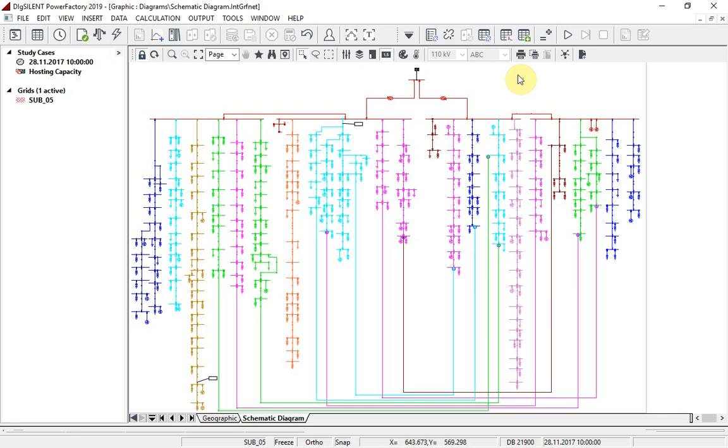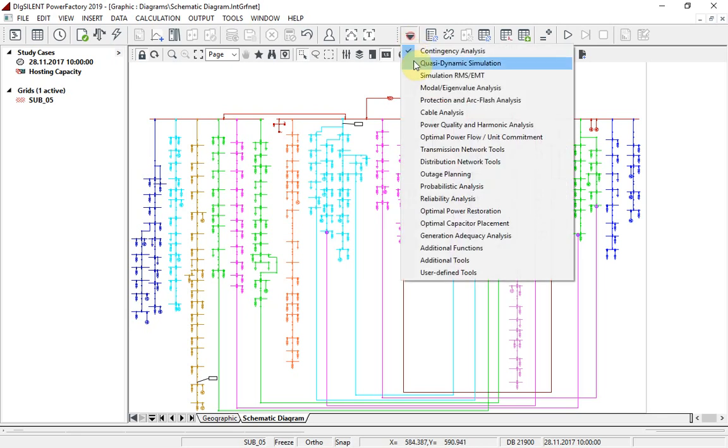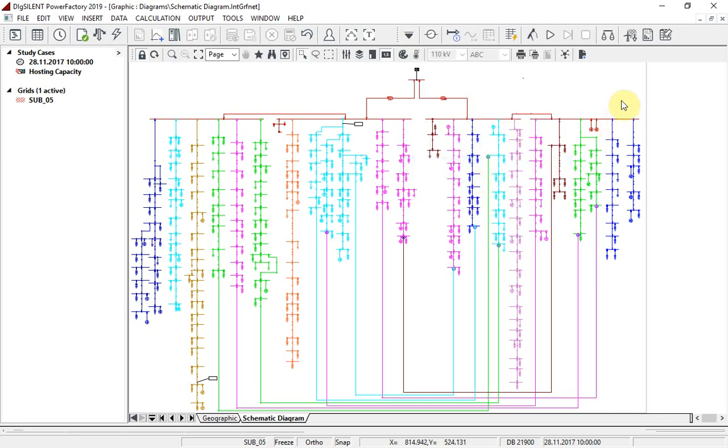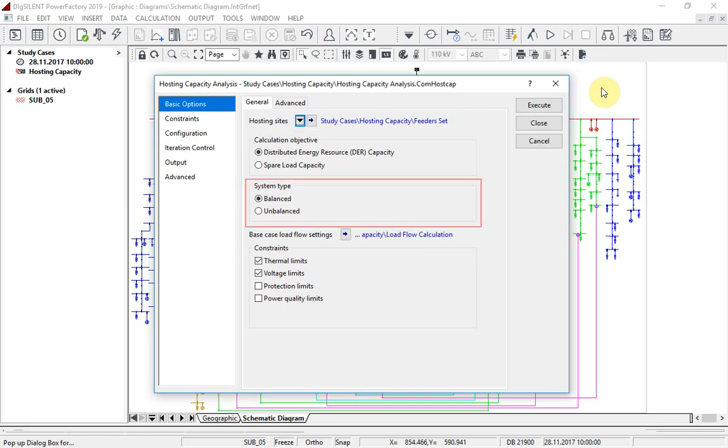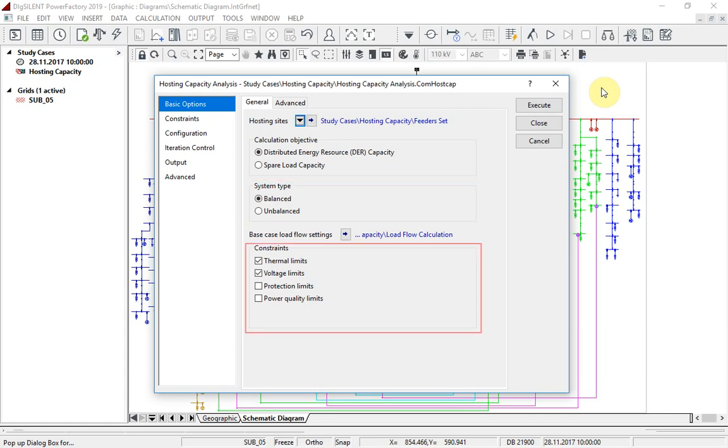Hosting capacity analysis is accessed via the distribution network tools toolbar. The calculation objective must be selected - distributed energy resource (i.e. generation) or spare load capacity - and the system type is specified. Then the relevant constraints are selected here.